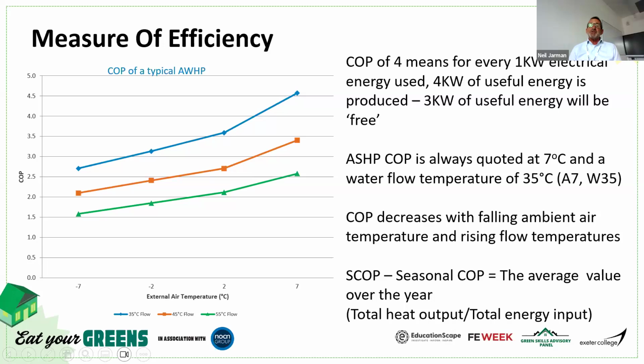So yeah, with regards to the COP, it's always quoted at A7W35. Now, A7 is a 7-degree ambient air temperature and a 35-degree water temperature. Now, that's a perfect scenario. So if you look at any manufacturer's instructions or data sheets, you will see it always listed at A7W35.